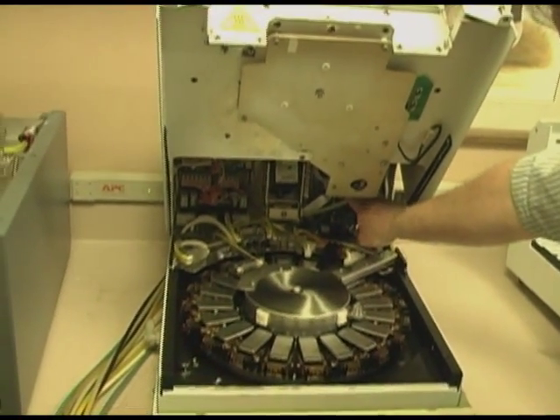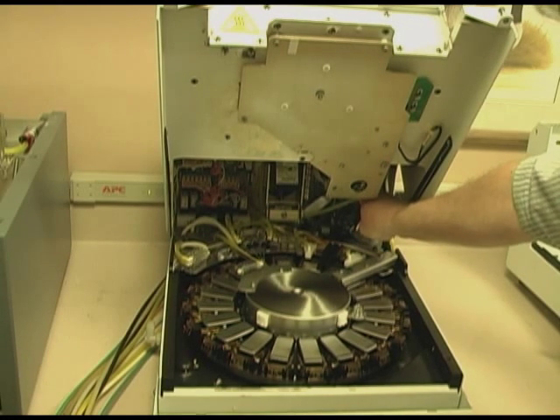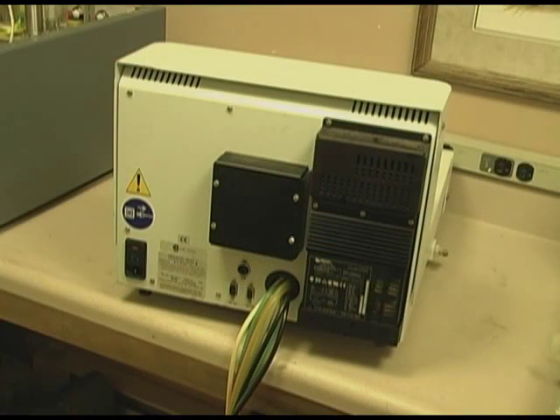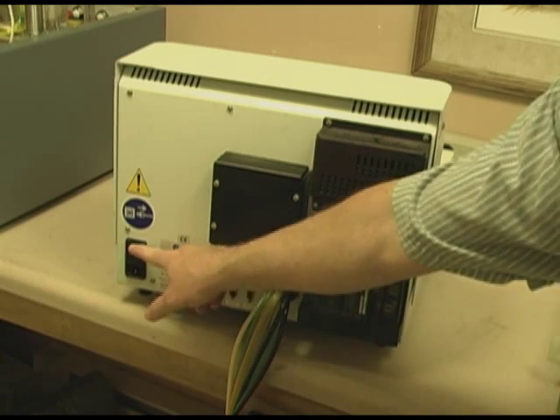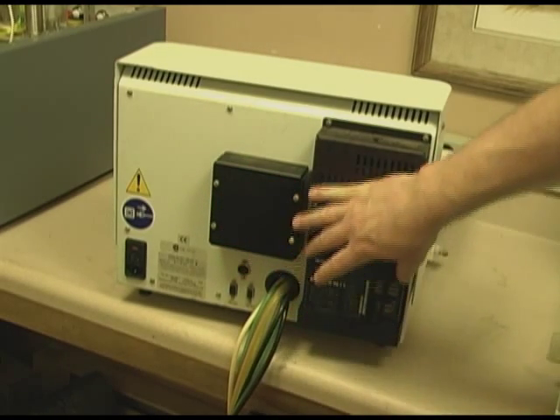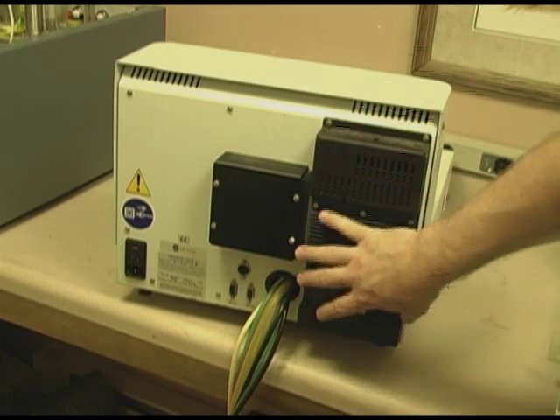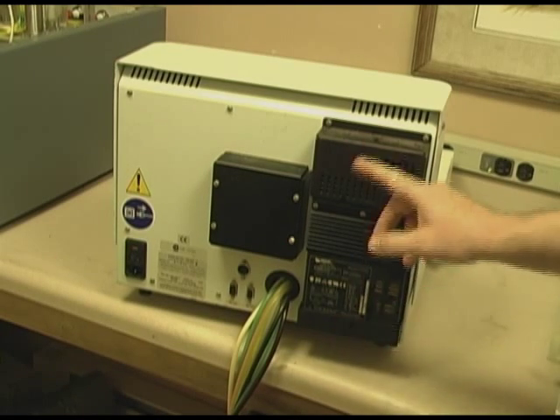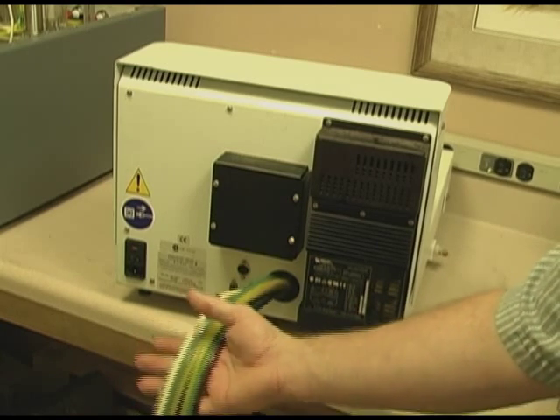You have a microprocessor control board right in the back here. Moving on to the back — it's relatively simple. On-off switch, and you've got two fuses in here. Right here is your power module — a few screws and that whole assembly pops out fairly easy. Input comes in down here and the output down here. This is where all your reagents and so forth come into.